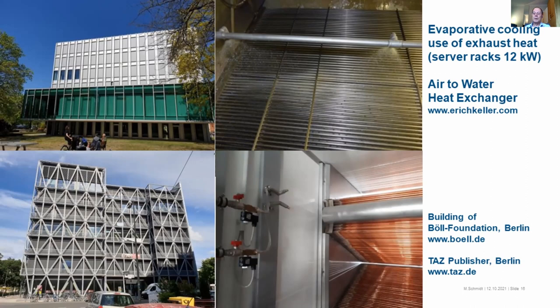We can, in the wintertime, use the exhaust heat from computers to heat buildings. So it makes no sense that, for example, for these buildings with 12 kilowatts in our server racks, you additionally invest 6 kilowatts to get rid of this energy in summer and winter. Always try to evaporate water to cool computers and to cool your building.